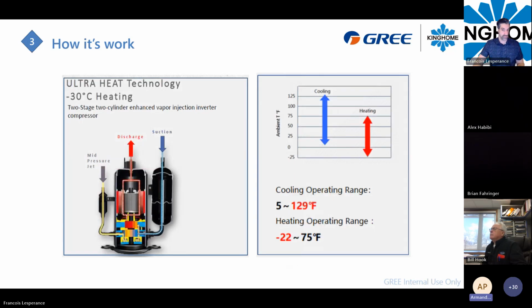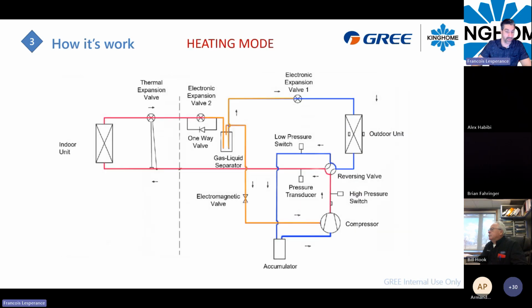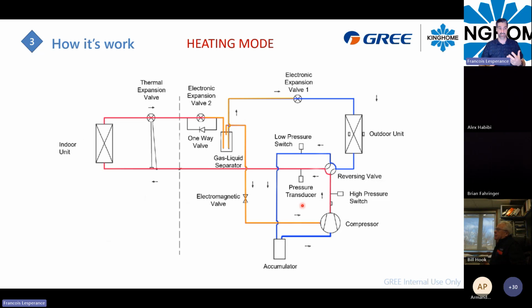Go ahead. Whenever we are using this heating mode, how will the unit determine that the outside temperature is too low and it has to inject some vapor from that accumulator to the compressor? Well, the algorithm of the system is built on a sensor that senses the outdoor temperature, and you will also have a pressure transducer right here that will give the system information about the pressure. It's an algorithm already built in the board of that unit, and when you hit this kind of parameter, because the pressure is too low and the outdoor temperature is too cold, this electromagnetic valve will open for a couple of seconds and it will inject hot gas in the compressor.